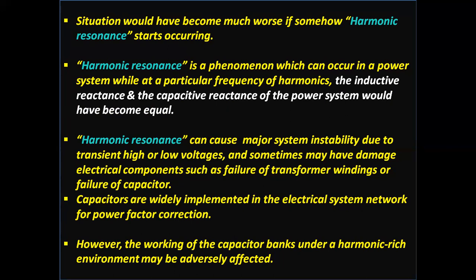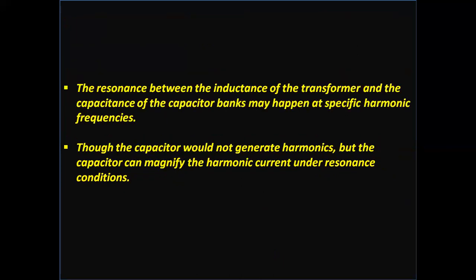Capacitors are widely implemented in electrical system networks for power factor correction. However, the working of capacitor banks in a harmonic rich environment may be adversely affected. Resonance between the inductance of the transformer and the capacitance of the capacitor banks may sometimes happen at specific harmonic frequencies. Though the capacitor does not generate harmonics, it can magnify the harmonic current under resonance conditions. Most important.